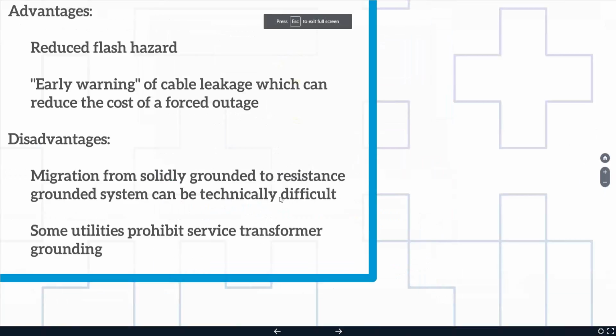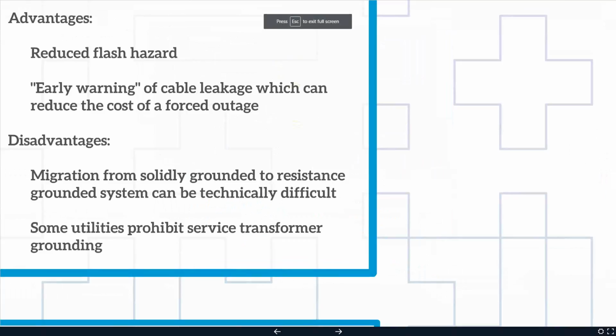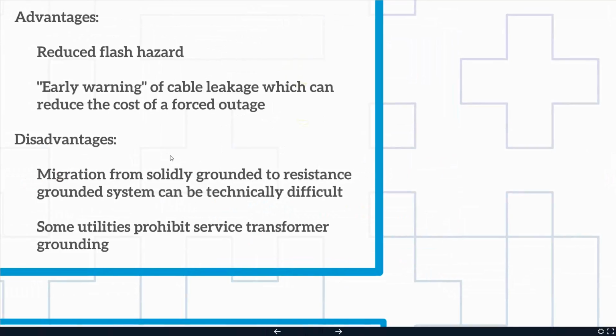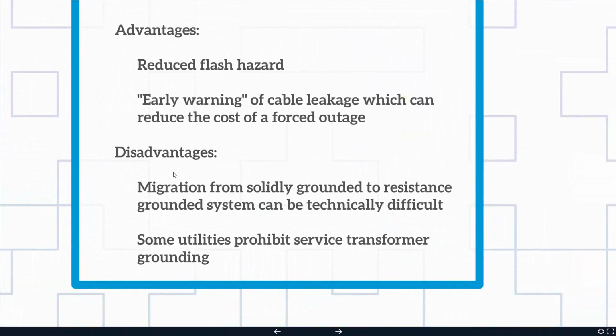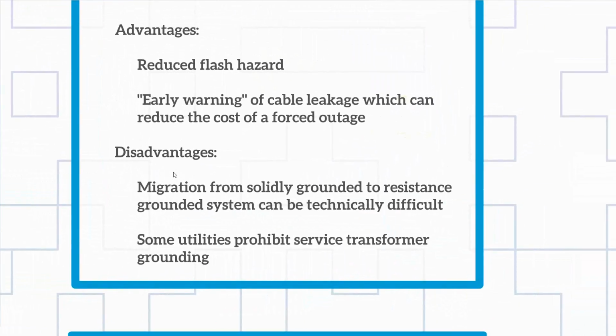So what you're saying here, oops, it looks like I lost my Prezi again here. It can be subtle. One of the headwinds we also face is when you're going from solid to resistance grounding, if you've got a typical main-tie-main into a campus system, the space for the resistor is the least of your problems, but how you deal with the existing cable, for example, some of the cable may not be 133%. You have to look at the shielding and the health, so to say, of the return back to the sensing element, back to the powerhouse.